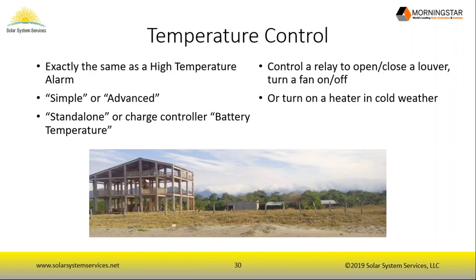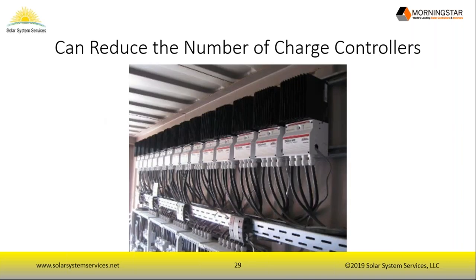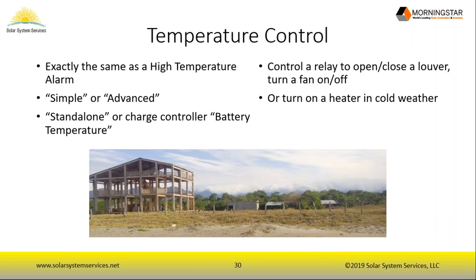Temperature control features work the same as the high temperature alarm — simple or advanced, standalone or based on battery temperature from the charge controller. Practical uses include turning a fan on and off or opening and closing louvers to manage enclosure heat — for example, one channel for louvers and another for fan control. Heating loads are generally avoided in off-grid systems as they waste energy.